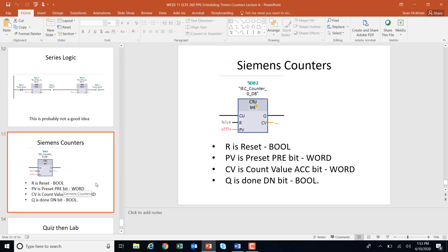Siemens counters are pretty straightforward — they go in as a block instruction as well. You have a reset, your preset value (a word), CV (count value), and Q (the done bit). This works just like Allen-Bradley: make CU true and it counts up; false, true — it counts up again and keeps counting. When the CV (count value) hits the preset, Q is done. It might be a good idea to take the Q and turn on a bit instead of using the counter dot Q directly.